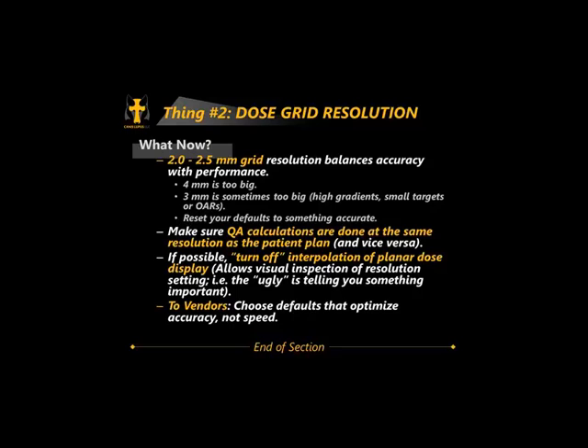Some planning systems have a default grid resolution of 4mm — and I will go on the record saying that's a poor default. A vendor may argue they let the user set it to whatever they want — and there's some truth to that. But the problem is users assume the planning system defaults are adequate, and often they are not. If you can turn off visual interpolation of planar dose display — the ugly result could be telling you something important.